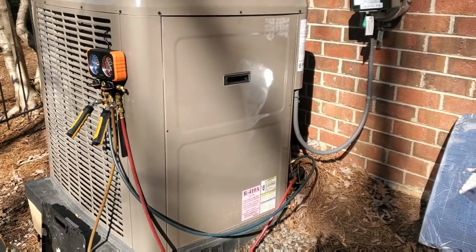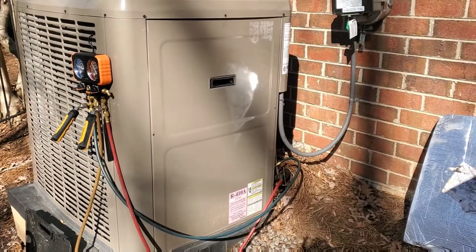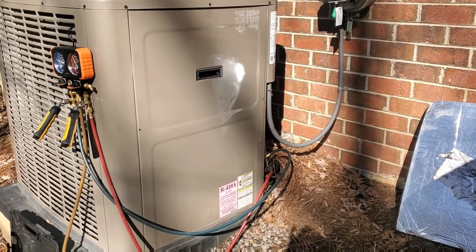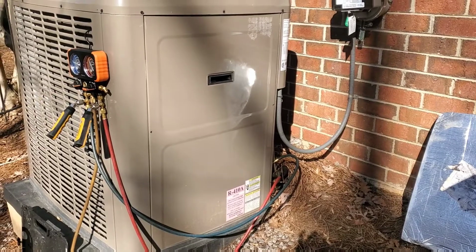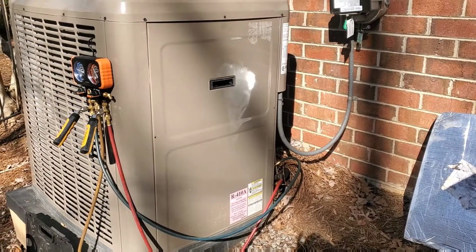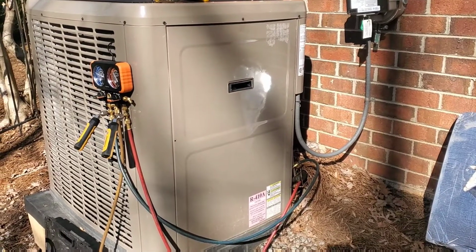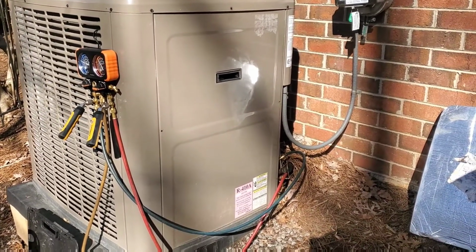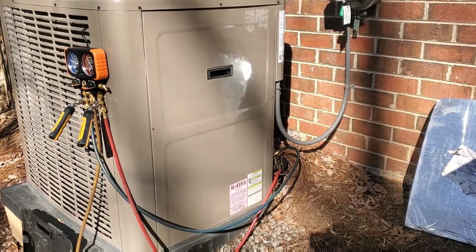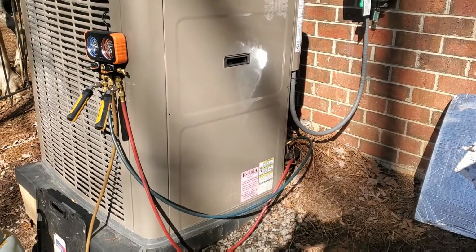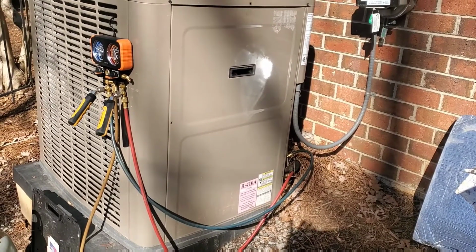When you're working on Carriers and their brand equipment, Goodmans, other brands where the compressor suction line is really not accessible, I get it. It's very inconvenient to try to get that temperature. Maybe if you're doing a non-invasive test, you can get away with not doing it as long as you're measuring other things like temperature rise, approach temperature. But when you're looking at the charge of the unit, you're specifically trying to fix a problem, you really need to give MeasureQuick all the information that it's asking for.